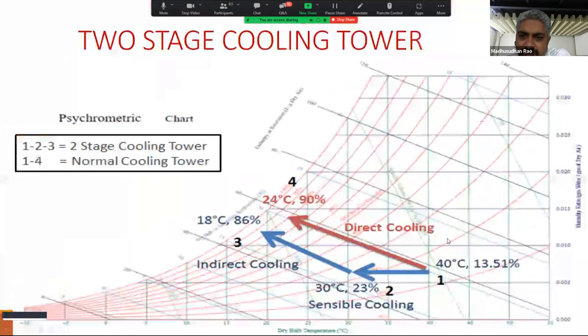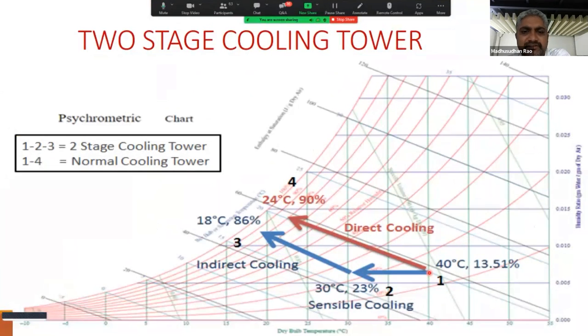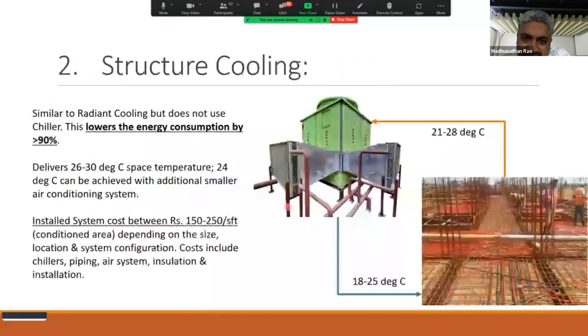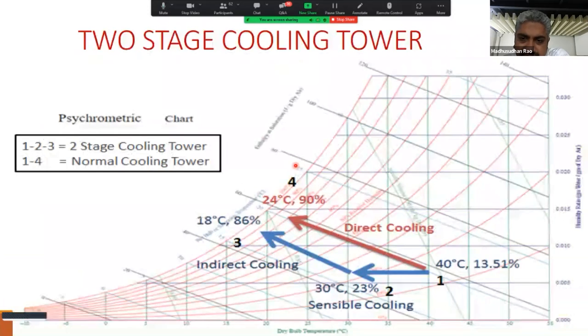So what would happen in your regular cooling tower is you would achieve wet bulb plus 2, plus 4, whatever, depending on the kind of cooling tower you have offered. There are cooling towers which can give wet bulb plus 1.1 or 1.5. So let's assume you have a regular cooling tower which gives wet bulb plus 4. So you will achieve 24 degrees centigrade, right? This is what you get. But let's say I increase the capacity of the cooling tower a little bit, and some of that water I circulate in a heat exchanger before the air comes into the cooling tower. So you will follow this path first, right? The air will get cooled. Its absolute humidity is not changing because it's indirect cooling, right?